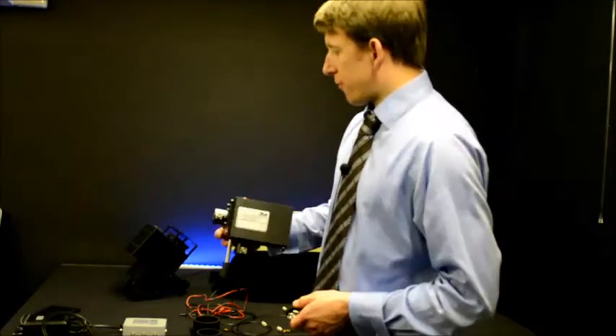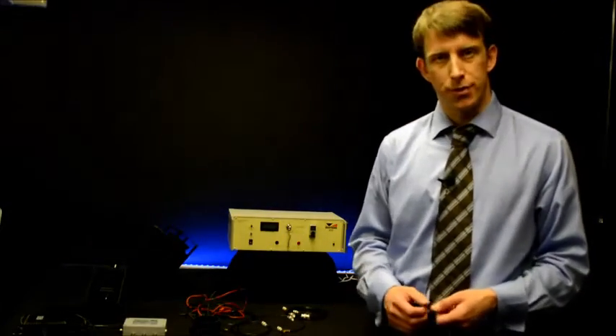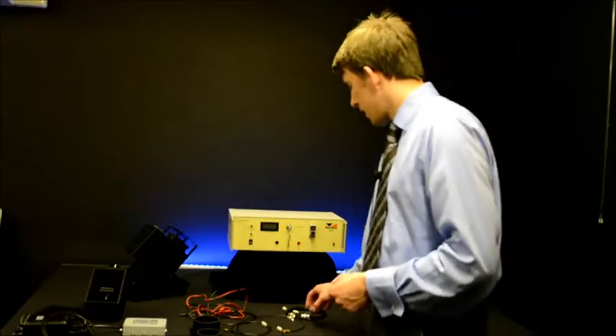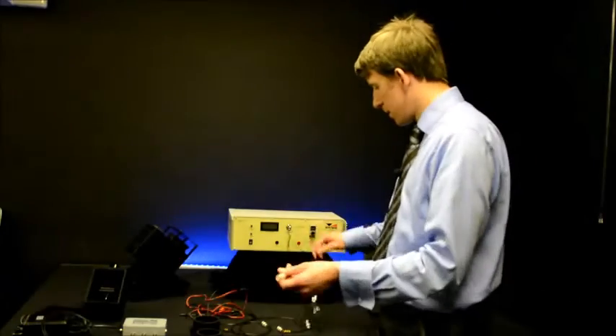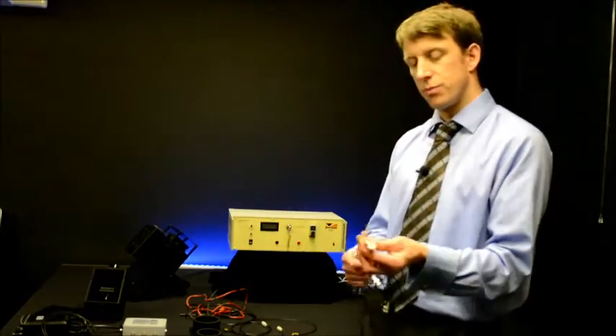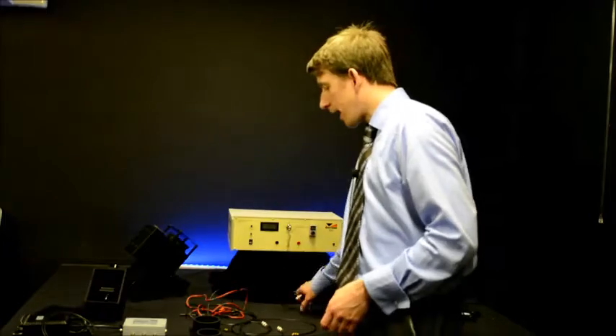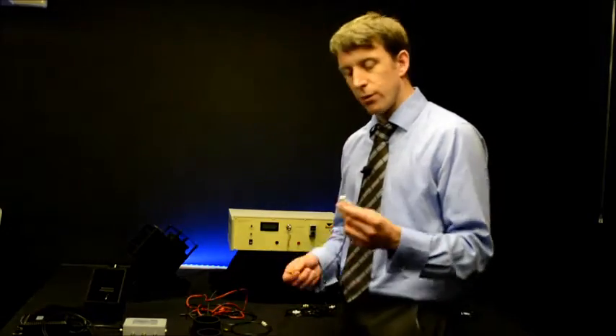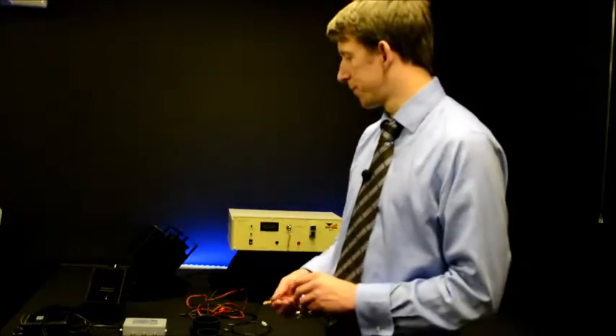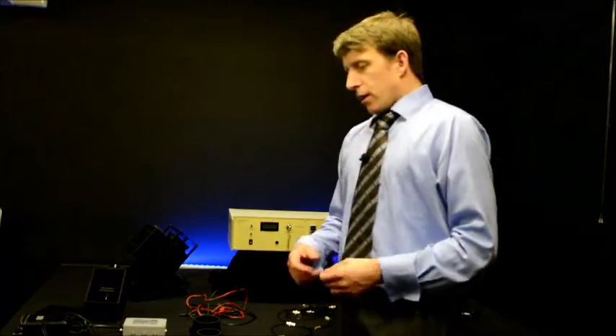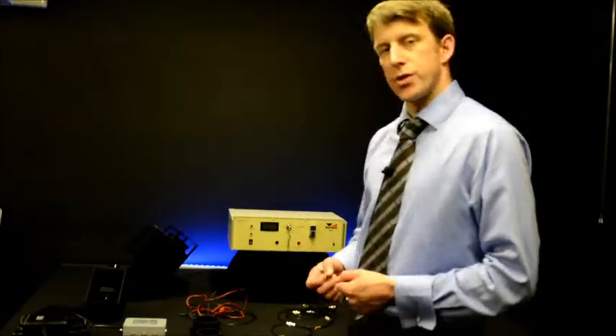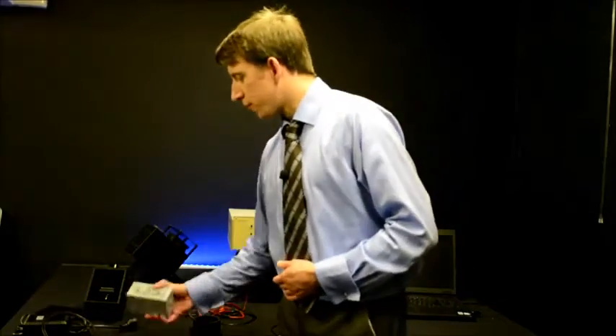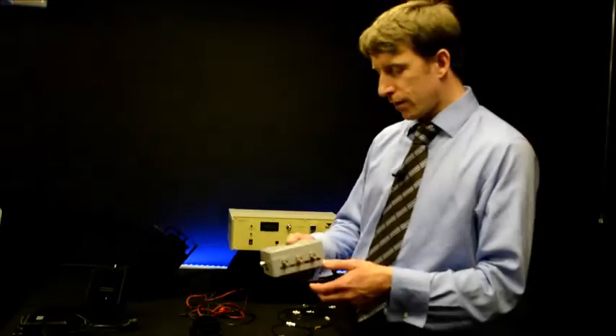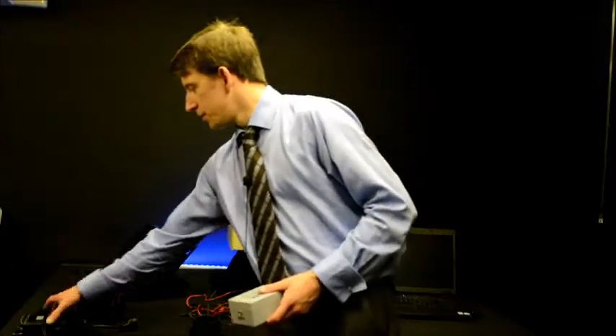The output of the reference and monitor diodes is a photocurrent which can be directly coupled to the detection electronics of both spectroradiometers. In the case of the DTMC 300 system, the signal is coupled by a BNC to BNC connectorized cable. In the case of the DMC 150 system, we have a BNC to SMA connectorized cable. In measuring radiometers, most of which will generate a voltage output, one should use the 472 module to interface to the detection electronics of the spectroradiometer. This unit has a power input provided by a transformer.